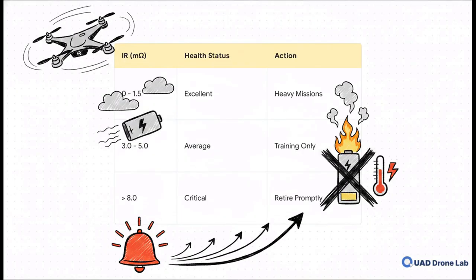So what numbers should you look for? A brand new industrial cell should sit below 1.5 milliohms. As it ages, it creeps up to 3 to 5 milliohms, and you'll start feeling voltage sap. But if the cell crosses that 8 milliohm threshold, retire it immediately. The heat generation at that point is critically unsafe.